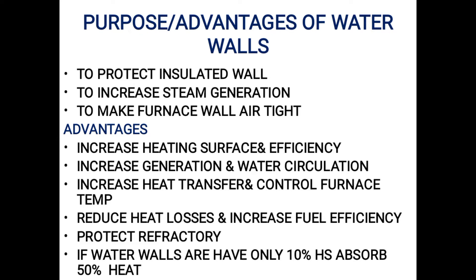Furnace temperature control is important regarding NOx control — by using water walls we can help control the production of NOx. Water walls also reduce heat losses, increase fuel efficiency, and protect the refractory. Notably, if water walls cover only 10% of the heating surface, they will still absorb 50% of the heat — this is a very important characteristic of water walls.